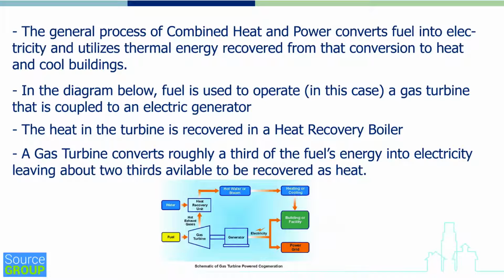In the diagram below, fuel is used to operate, in this case, a gas turbine that's coupled to an electric generator. The heat in the turbine exhaust is recovered in a heat recovery boiler. That generates either steam or hot water, and that is piped to the building, where it's used to cool or heat the building, and also in cases of cooling, it's used for reheat purposes during the summer months.